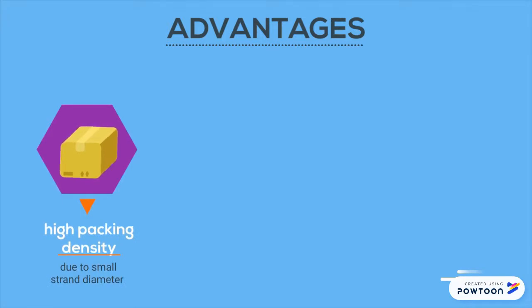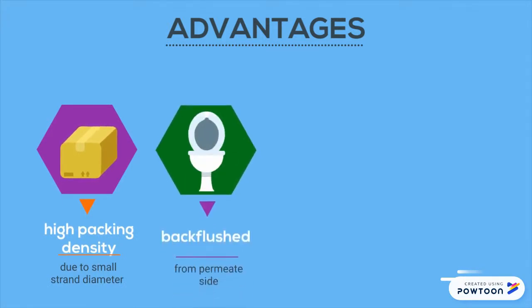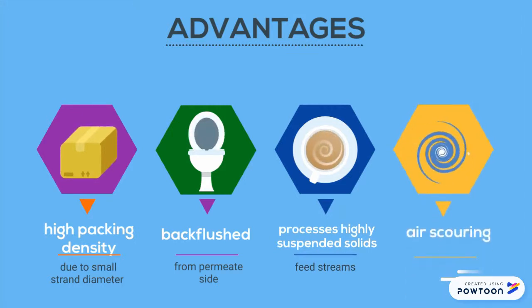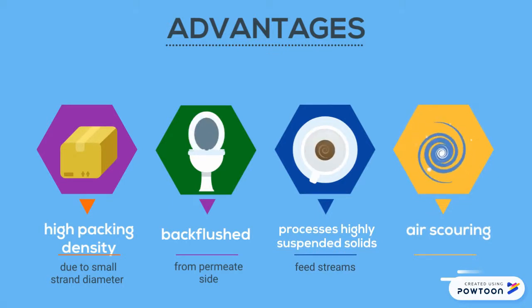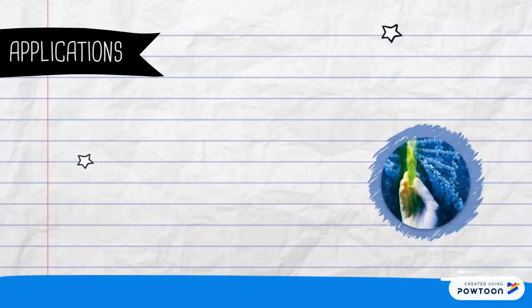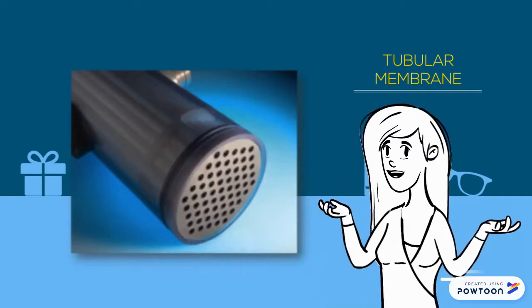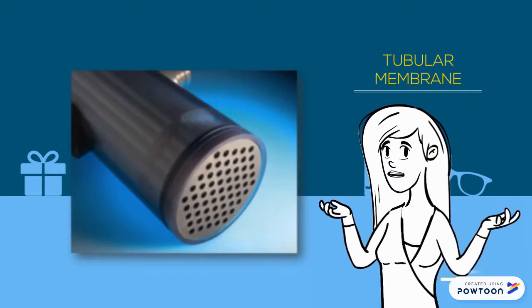Advantages of hollow fiber membranes include a very high packing density due to the small strand diameter, and the flexibility of the strands allows specific filter configurations not achievable in other filtration configurations. They can also be back-flushed from the permeate side and air-scoured, and can process feed streams with highly suspended solid particles. Common applications include reverse osmosis pretreatment, wastewater treatment, food and juice production, and biotech applications.